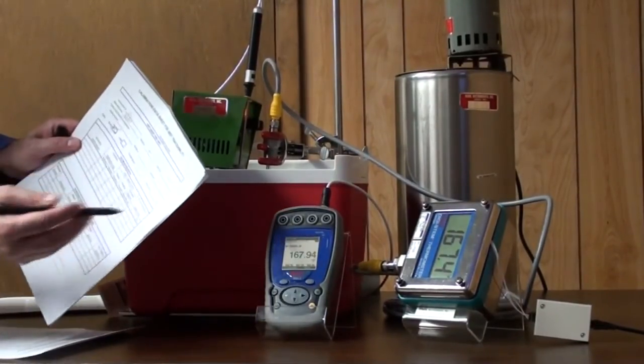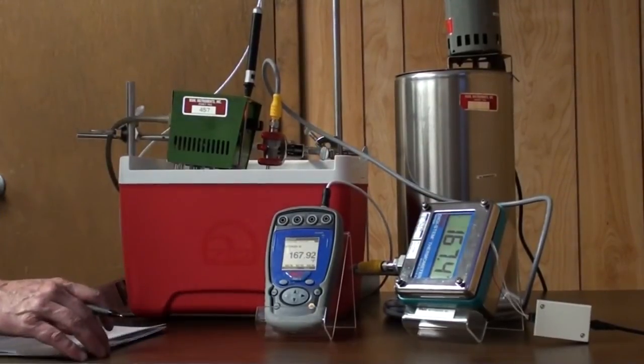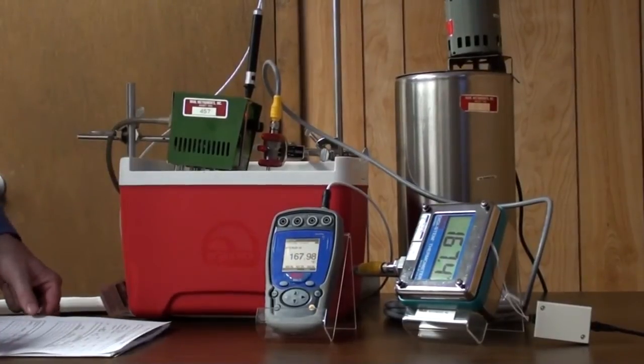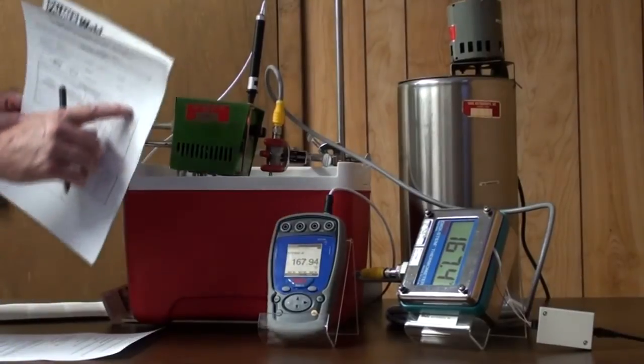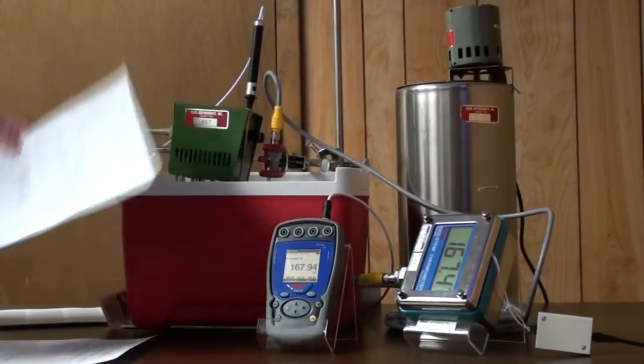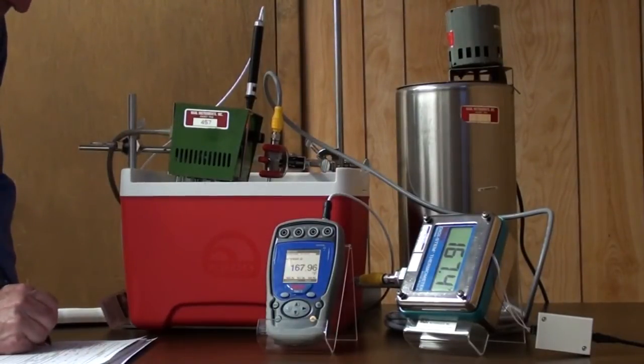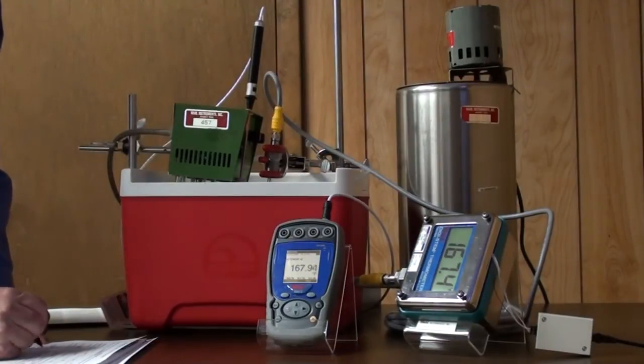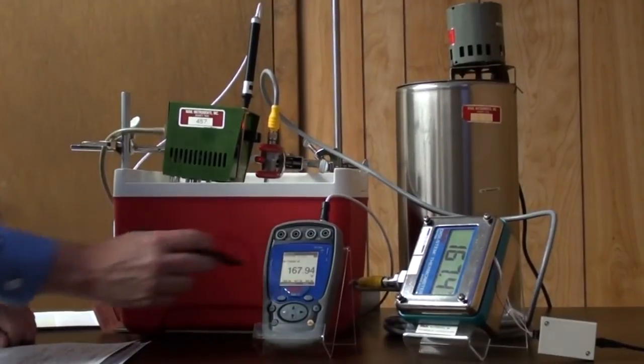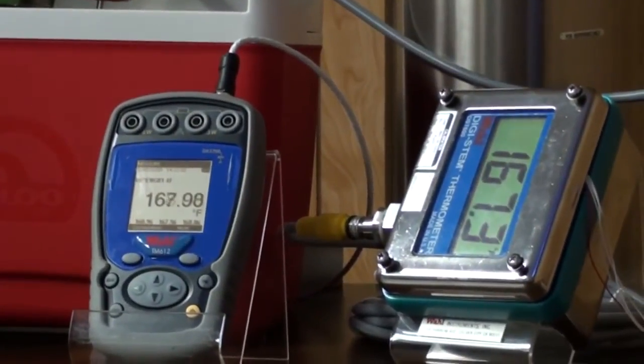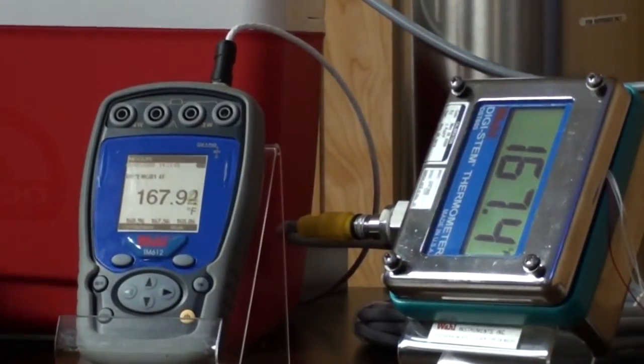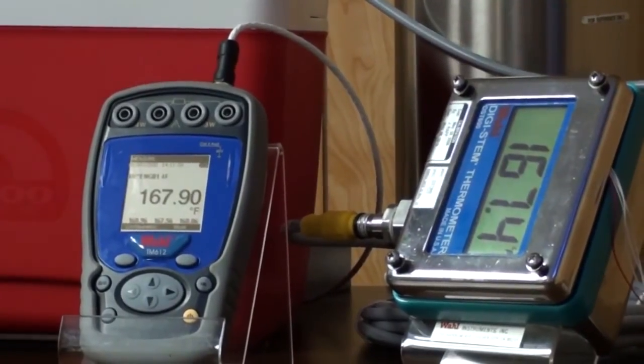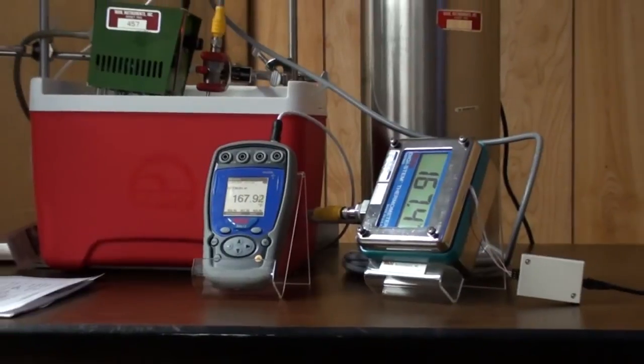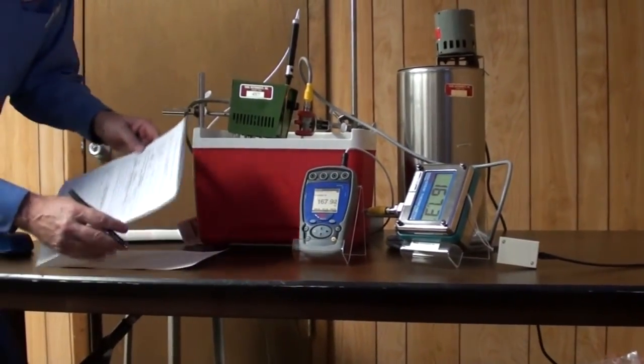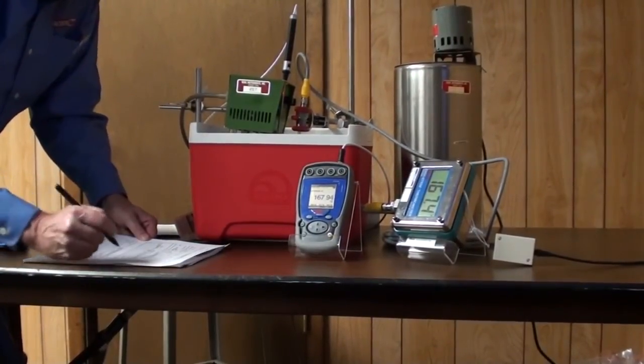I would record the ambient temperature and the humidity from a standard instrument again, and I don't have one here. We have them in all our labs and production areas. And then that standard instrument technically is also part of your standard instrument description down here. So I'm ready to take data. I'm in a water bath, and my nominal temperature is 170 degrees Fahrenheit, and our actual temperature is 167.94. Our display reading is 167.4. Now our deviation from our procedure, we said it was 0.3 of 1 degree Fahrenheit. So my allowable deviation is 0.3 F, 0.2 F after. So my display deviation in this case is 0.54 degrees, so that would be out of tolerance.